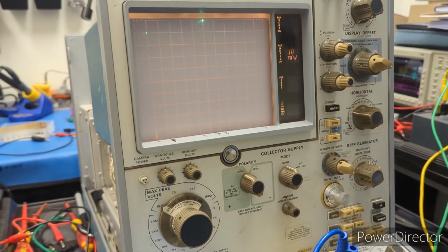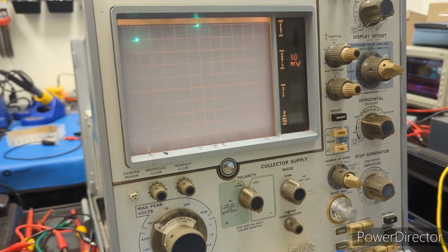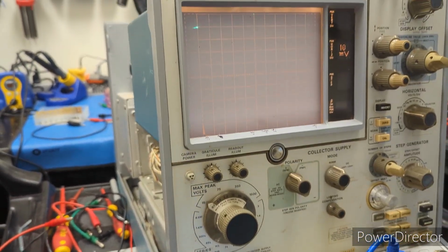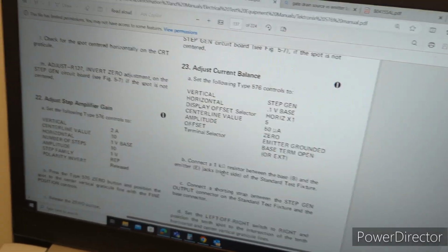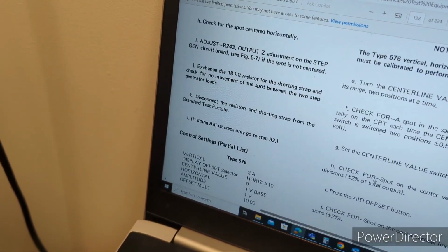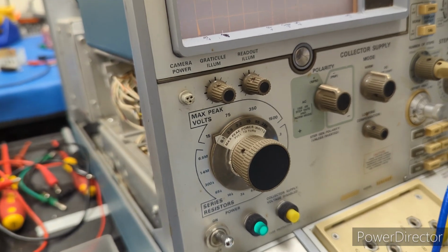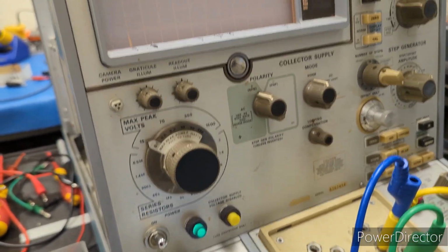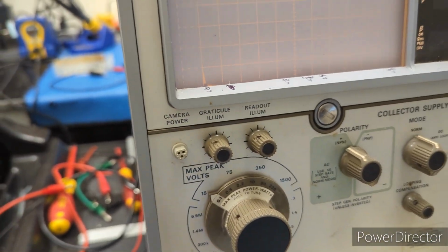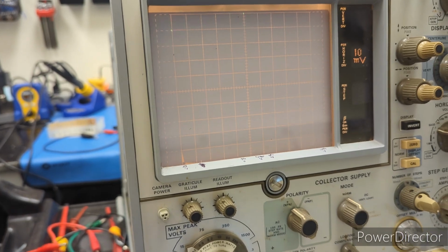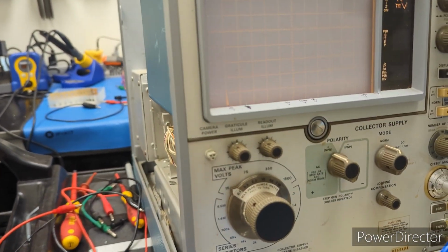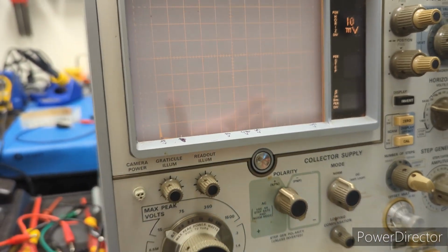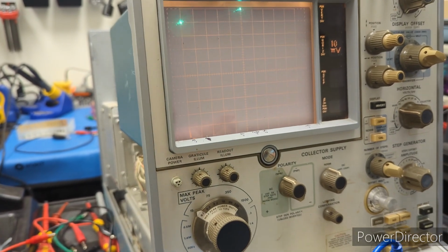All right, so I've gone back and looked over all of the first portion of the performance check calibration procedure, and got all the way up to step 23, which is adjusting the current balance. That step looked great, by the way. And if you're doing the adjust steps only, go on to step 32. Step 32 is the loop compensation, which we just did not long ago. So I think this means we are good to go as far as the calibration goes. We were able to fix the PNP and NPN positioning by doing some adjustments with the vertical and horizontal display amplifier.